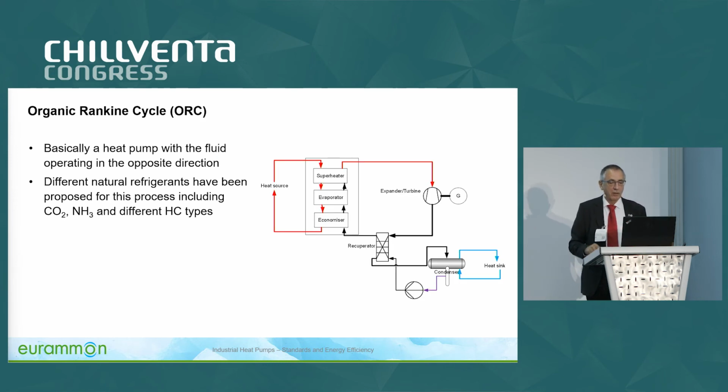There are, of course, also other ways to reuse heat. You have the organic Rankine cycle. It is still a little bit of a niche, and the amount of heat we can recover this way is around 18 to 25%, depending a little on what you look at. There are hydrocarbons that can cover the same area as we have done in the past with R245 and whatever they are called, R236. We can do that also with hydrocarbons, and even safely.